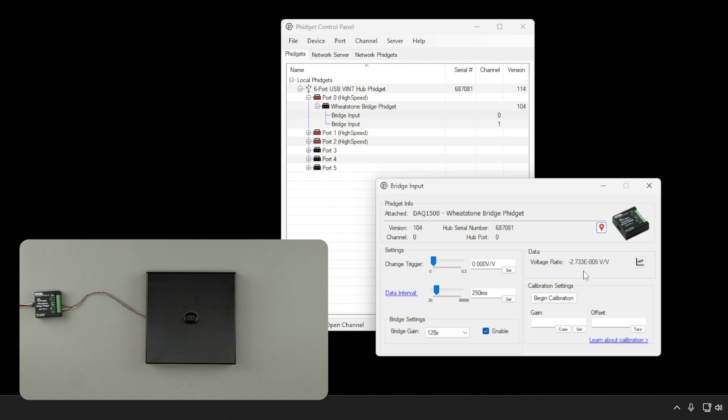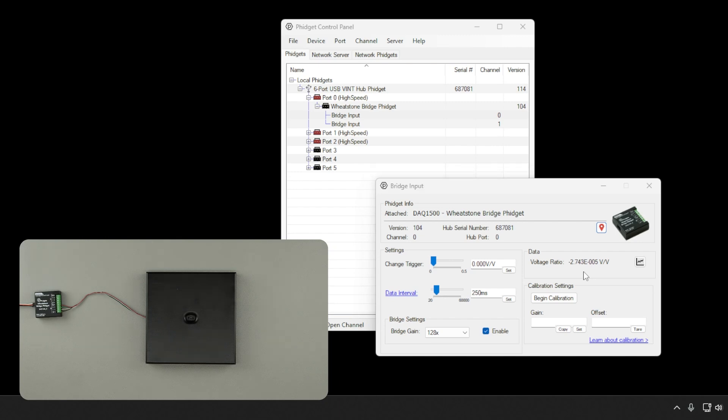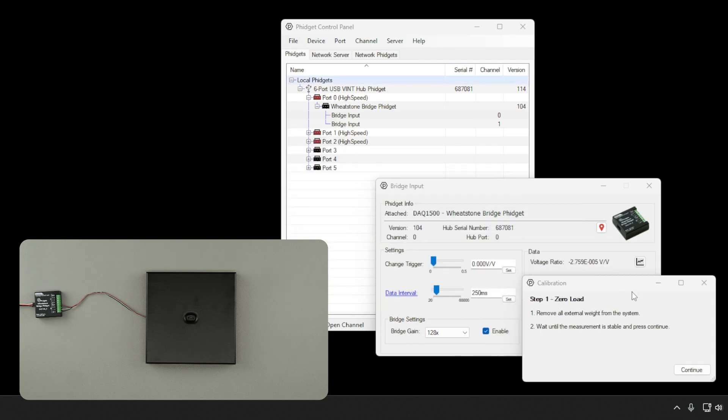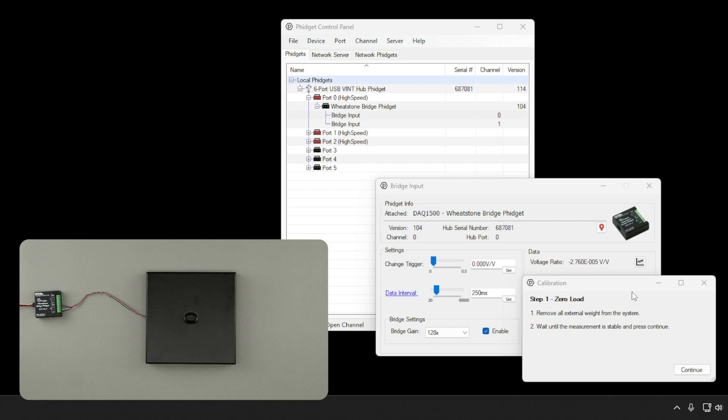This is a simple process where we collect two data points. One when the system is unloaded and the other when the system is loaded with a known weight. We can start by pressing the Begin Calibration button. The first data point we'll collect is when the system is unloaded or, in other words, when the system should output 0. This calibration point will help remove any offsets associated with your system. When you're ready, press continue.